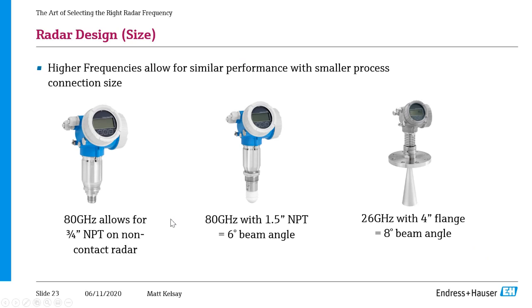This is also good in small vessels. Small vessels typically are a little crammed on top of them, so being able to put a small process connection is very beneficial. If you compare the two on the right now, what I'm looking at here is we've got similar beam angles, so a 6 degree with the 80 gigahertz unit and an 8 degree with the 26. However, you can see the drastic difference in the size of the connection. So with high frequency, we can do this with a 1.5 inch NPT, very small unit. But with the 26 gigahertz, it's going to take a 4-inch flange and a 4-inch antenna to get that similar performance in terms of beam angle. So these devices become much more manageable in terms of size, makes the installation a little easier.